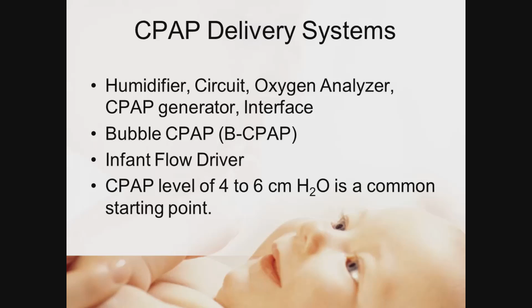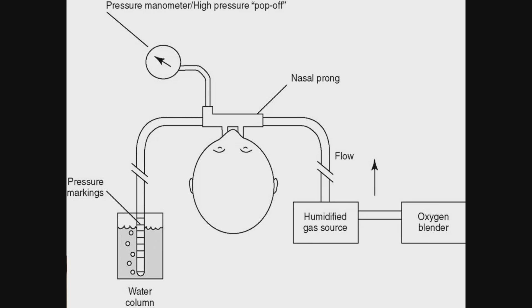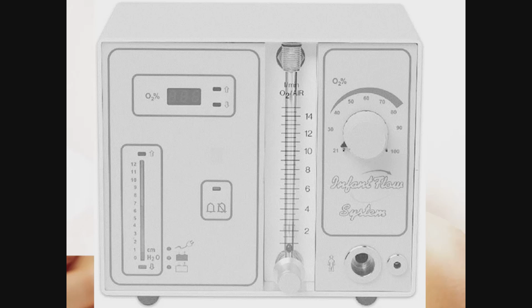This is, if you remember back, when you're talking neonatal, you had a gas source through a humidifier, nasal prongs attached, monitoring the pressure, and some kind of mechanism to generate it. This is just a bubble CPAP, just running some flow underneath water, and the depth of that hose tells us how much CPAP we end up having. This is the infant flow, excuse me, that allows for a preset amount of CPAP to be created. It's a little more expensive, obviously.